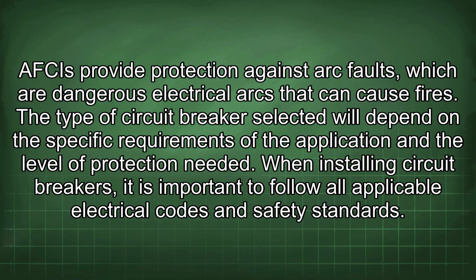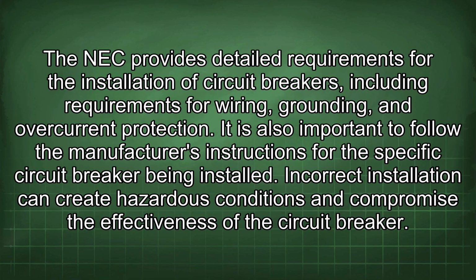The type of circuit breaker selected will depend on the specific requirements of the application and the level of protection needed. When installing circuit breakers, it is important to follow all applicable electrical codes and safety standards. The NEC provides detailed requirements for the installation of circuit breakers, including requirements for wiring, grounding, and overcurrent protection. It is also important to follow the manufacturer's instructions for the specific circuit breaker being installed. Incorrect installation can create hazardous conditions and compromise the effectiveness of the circuit breaker.